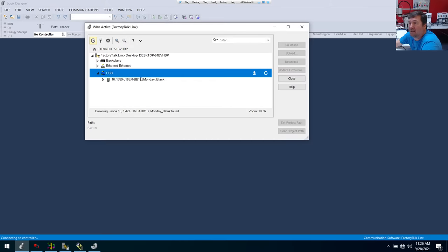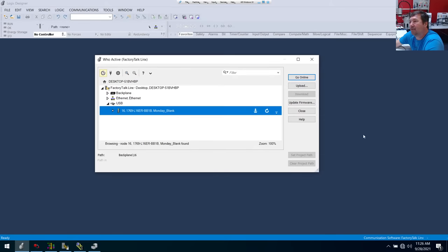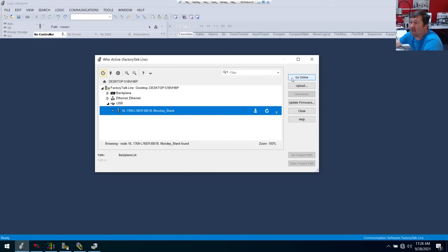And there it is. So we can click on our L16, and OK. If you notice I have no file open — notice my download button isn't there. That's a good hint that we're not going to download to the PLC. The only thing I can do right now is upload, go online, or I could update firmware. I kind of wish they would hide that button a little bit more. Really, here's where you want to be: in these three buttons. So if you have a file or you think you have the right file, go open it and try to go online. I don't have a file so I'm going to have to open one, or I could go online — let's go ahead and hit the go online button.